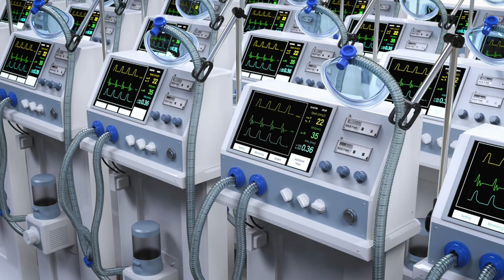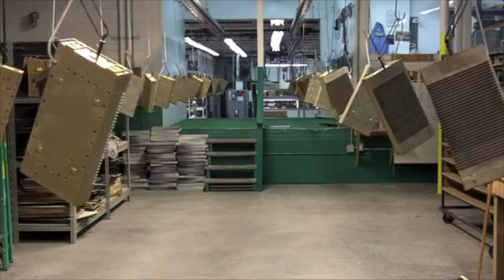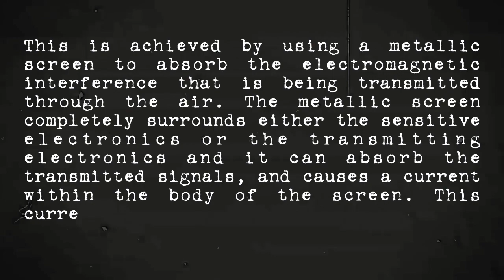By using EMI shielding, key components in medical devices like ventilators can be protected from electromagnetic interference and radio frequency interference, because this protects the sensitive signal from external electromagnetic signals or prevents the stronger signal from leaking out and interfering with surrounding electronics. This is achieved by using a metallic screen to absorb the electromagnetic interference being transmitted through the air. The metal screen completely surrounds either the sensitive electronics or the transmitting electronics, and it absorbs the transmitted signals and causes a current within the body of the screen. The current is later absorbed by a ground connection. By absorbing these transmitted signals before they reach the sensitive circuitry, the protected signals are kept clean of electromagnetic interference, maximizing shielding effectiveness.